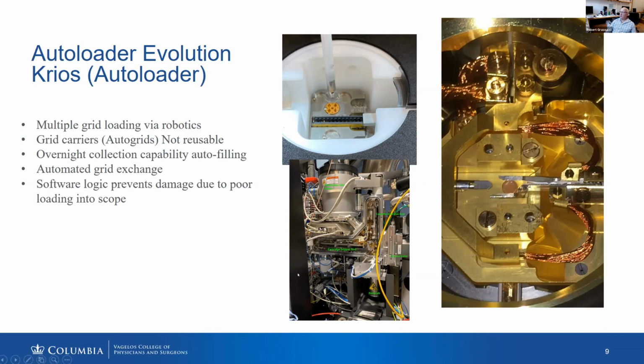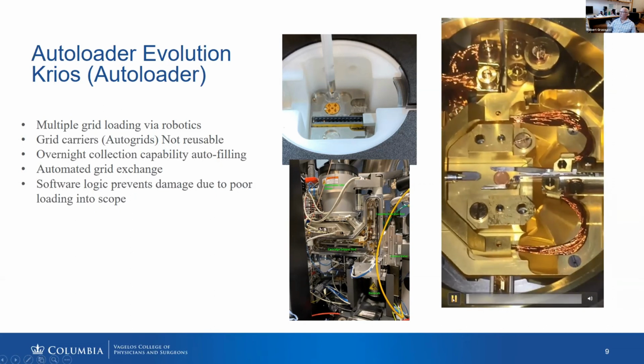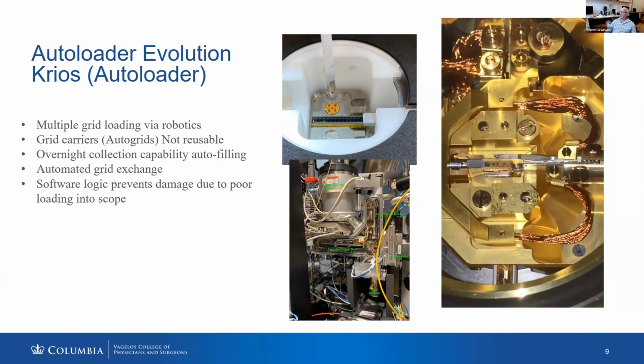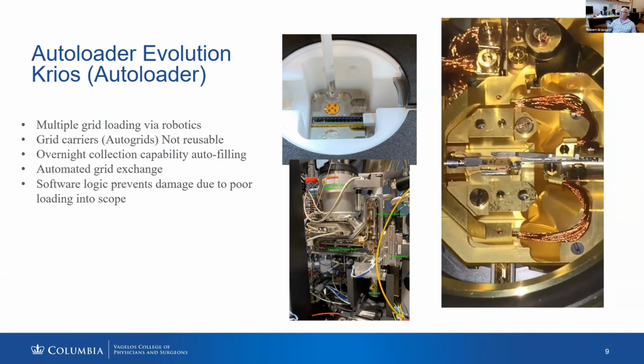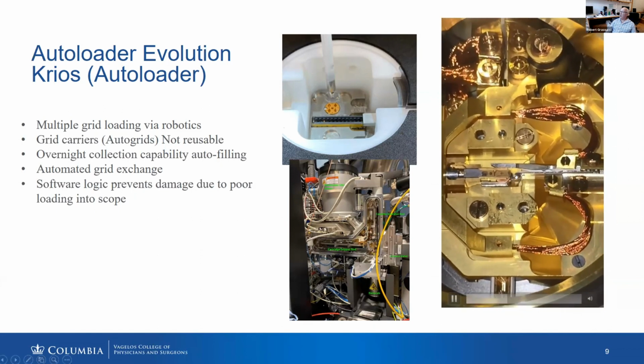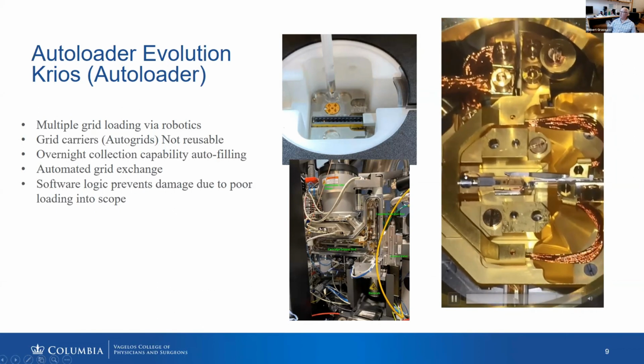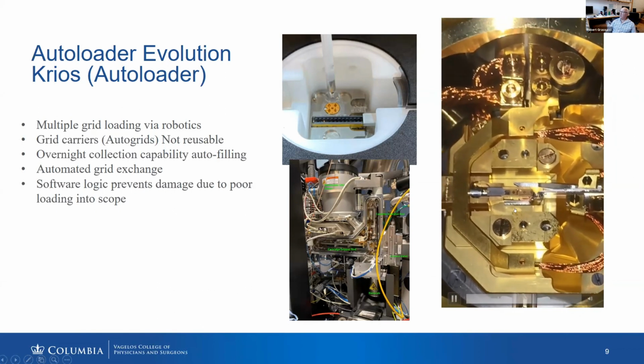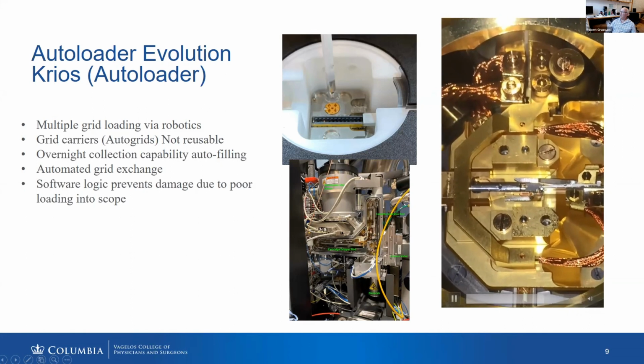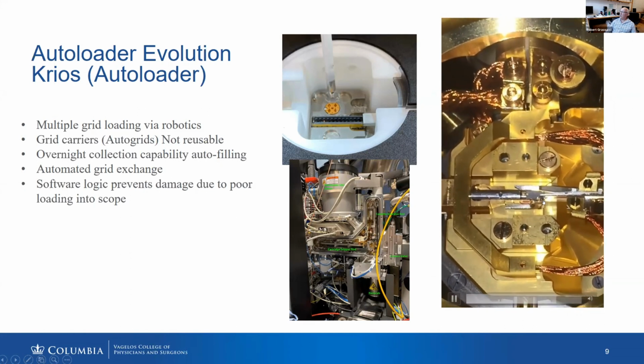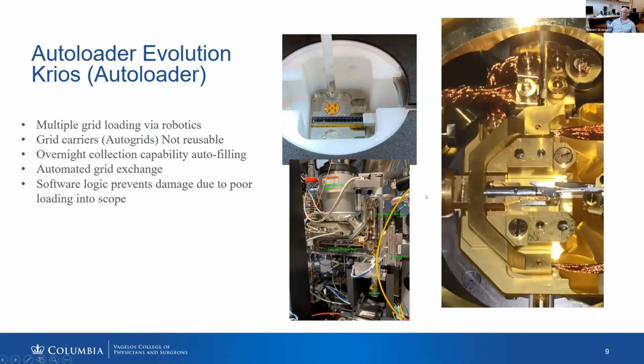This is the inside of the autoloader: the cartridge gripper rod, the cassette insertion rod, then the column over here. And here's a little video of exactly what's going on when you change the grid. The gripper goes in, it grabs the grid, then this guy slides in, clamps it, pushes this out of the way, and then pulls the grid out.